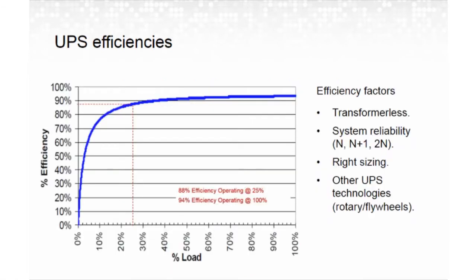So when you look at the efficiency curve of a UPS, at 100%, it's about 94% efficient, and this is kind of your typical older UPS. Some of the newer technologies, the newer IGBTs, the new semiconductors, transformerless UPSs, you'll see go up to about 96-97%, but there is still a percentage of loss at 100%. And as you go down the curve and the load gets less, you'll see a much greater drop in efficiency. So figure about 25% on the curve, you're at 88% efficient.